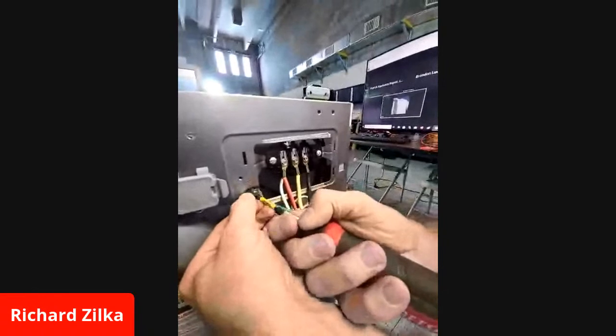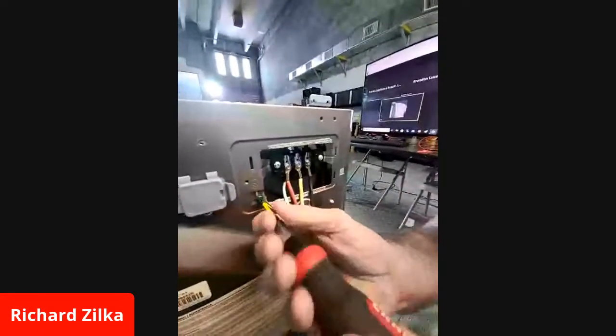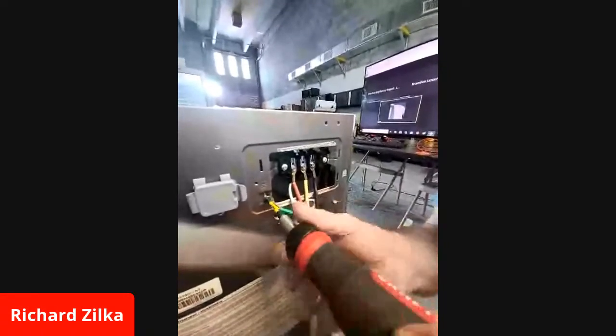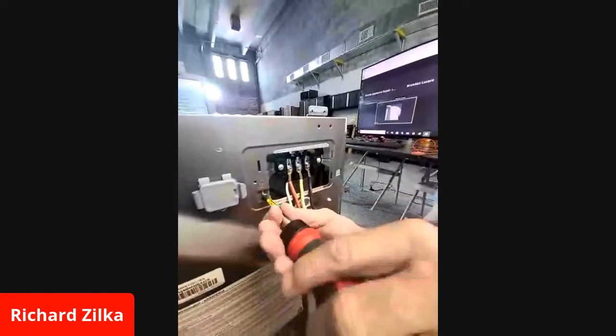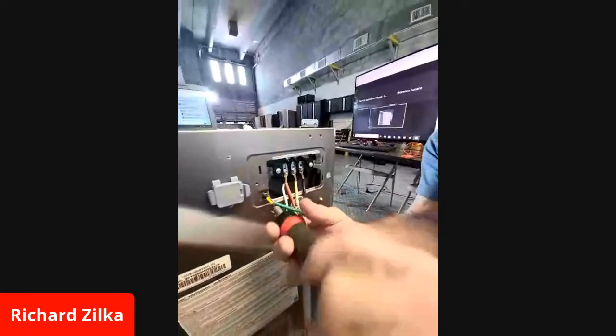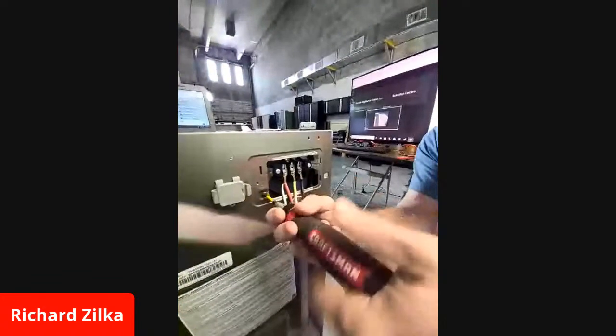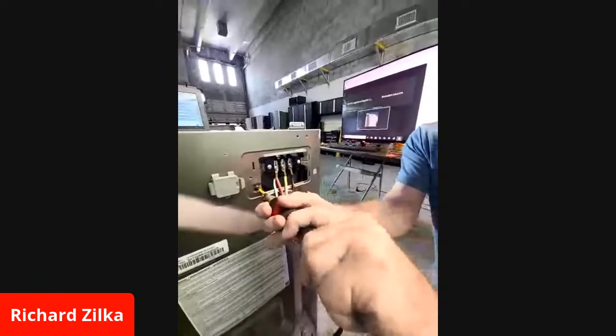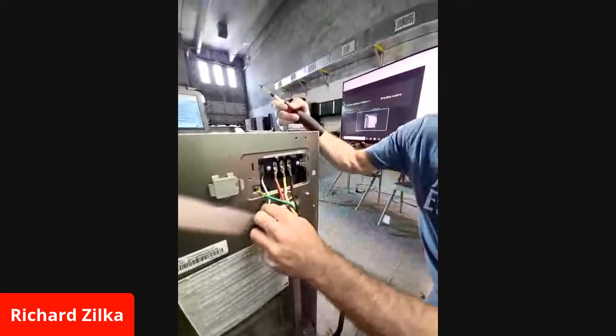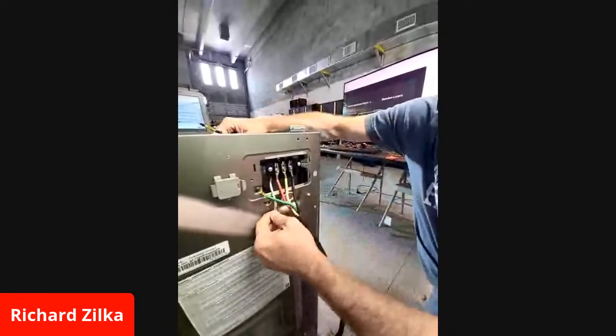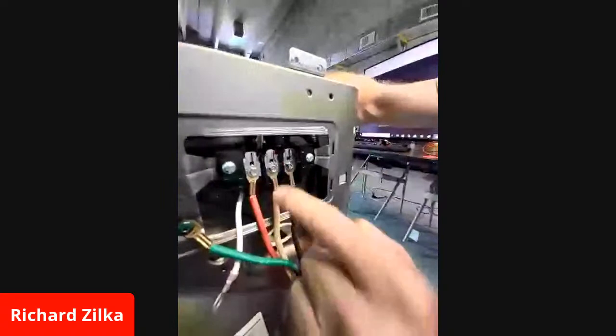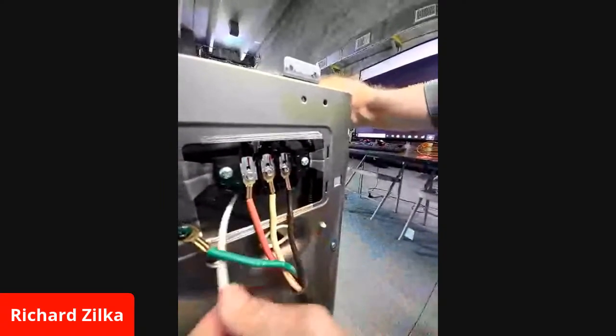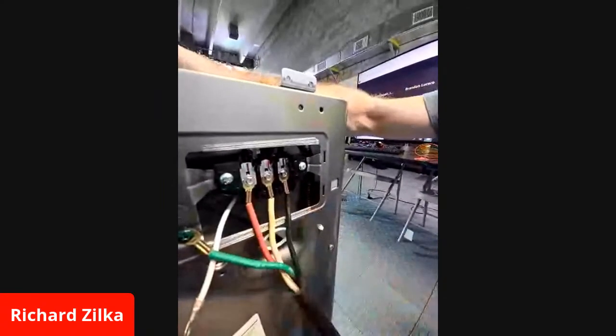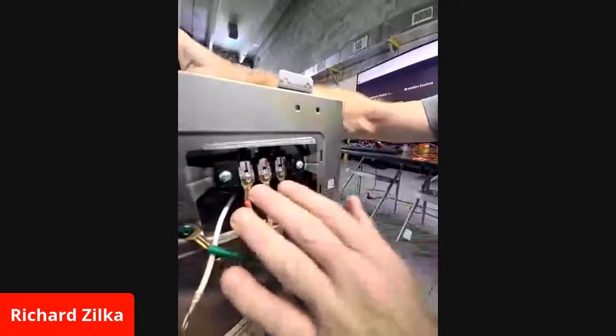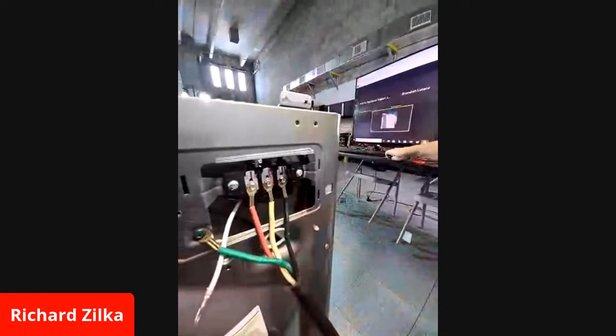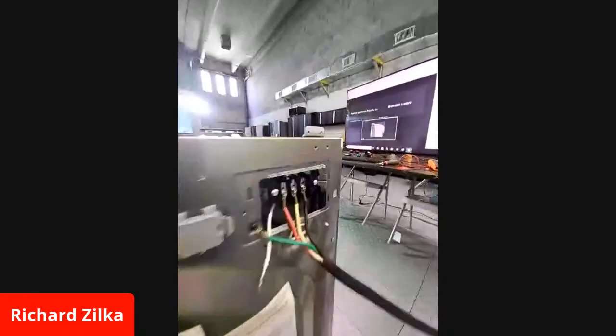The idea is that neutral and ground, even though in the panel they're the same thing, this allows you to separate the neutral and ground and give them alternate paths in case one breaks, the other one takes over. So on a 4-wire cord, this neutral here would be removed, and on a range, it'd be like a brass strap going from here to ground. So now this is the way it is. It's wired up properly, so we do have proper power at the outlet. Let's check proper power here and how to check the power at the input of the dryer.